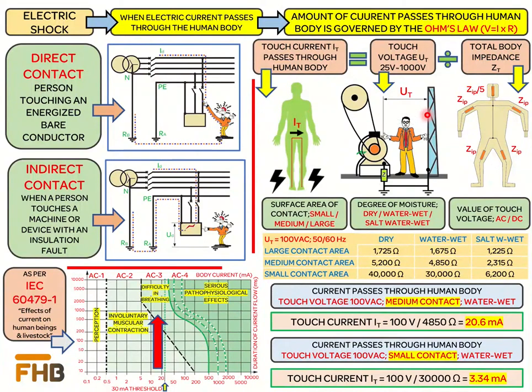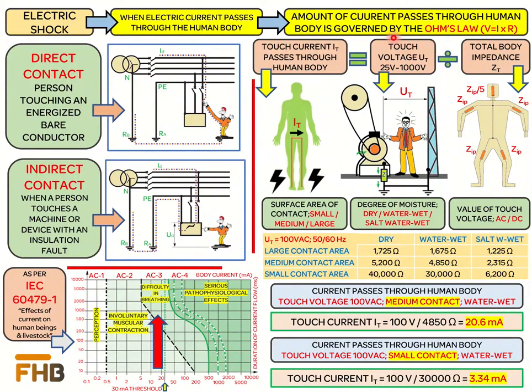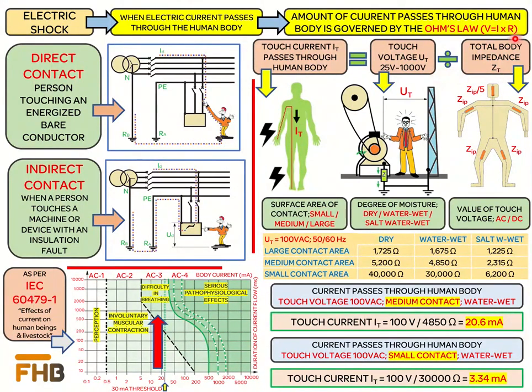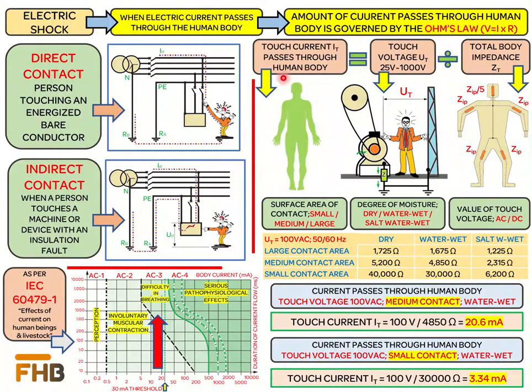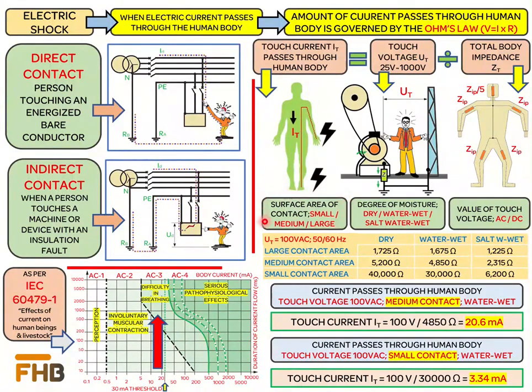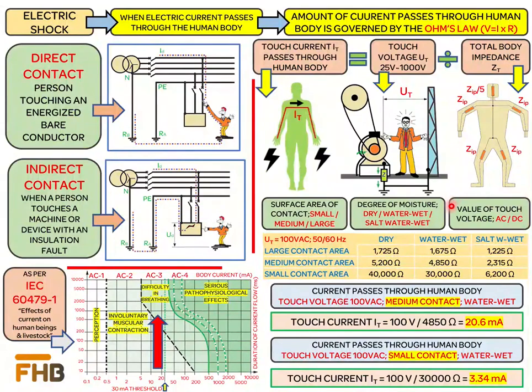As per IEC 60479-1, touch voltage is considered from 25 volts to 1000 volts and can be both AC or DC. The body impedance as per IEC 60479-1 depends on many factors — most importantly on the current path and the duration of current flow through the body, as shown in the picture. Other factors include the surface area of contact with live or faulty parts, the degree of moisture of the skin, and the touch voltage including its magnitude and type — AC or DC.